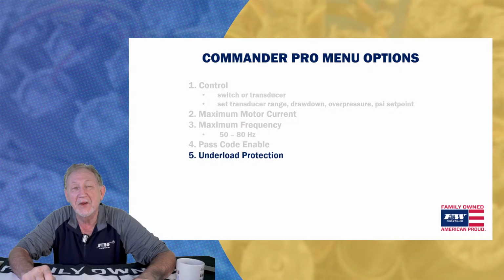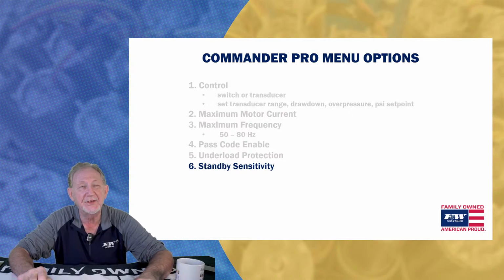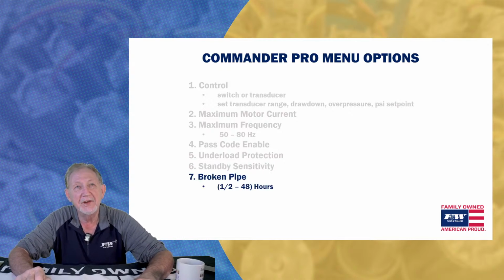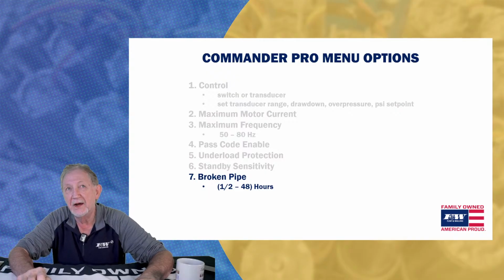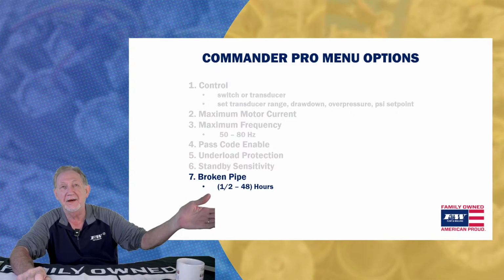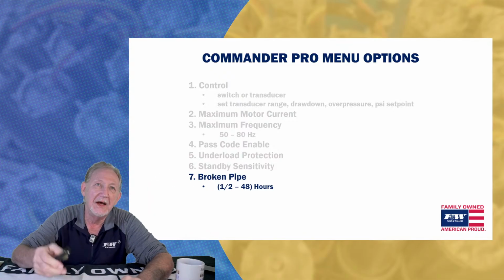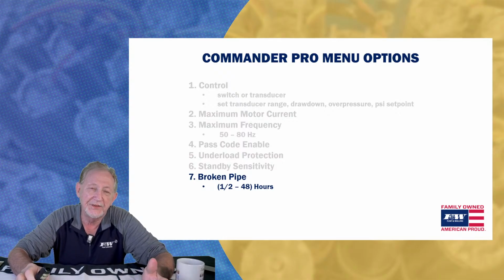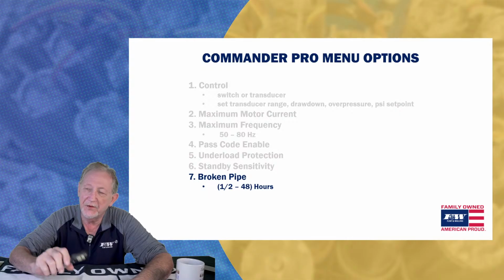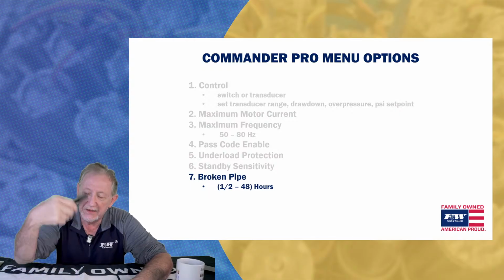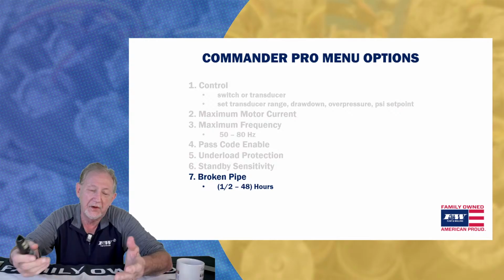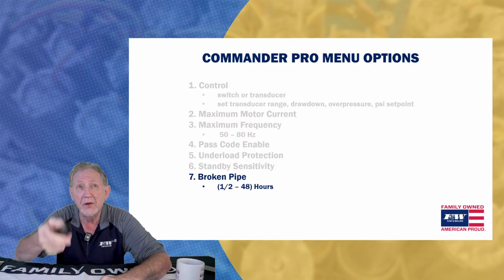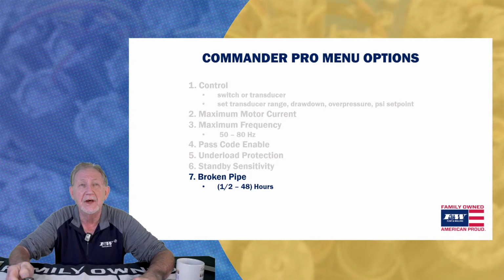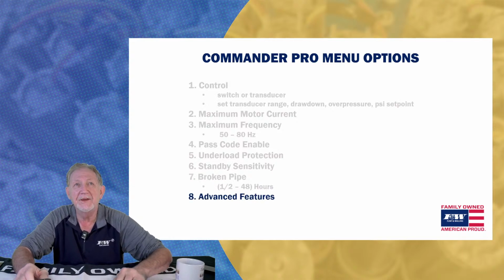Menu number 5 is going to be for underload protection. Menu number 6 is standby sensitivity. And number 7 is broken pipe. That's a simple timer that you can set to operate anywhere from half an hour up to 48 hours. In other words, if it's been set for 3 or 4 hours, and that pump has been running constantly for 3 or 4 hours, hasn't built up pressure, hasn't shut off, it's going to kick into a broken pipe mode. It's going to assume that you've got a broken pipe somewhere. You can also totally disable that function if you want to. Number 8 is advanced features.